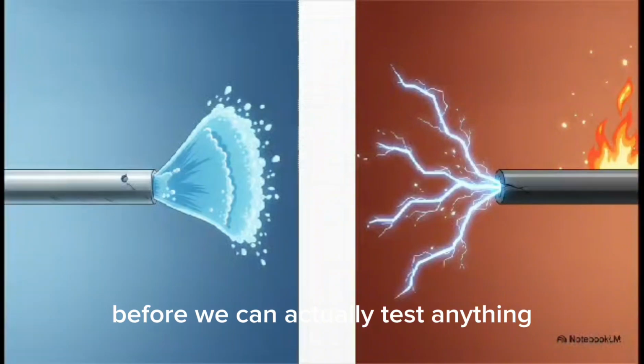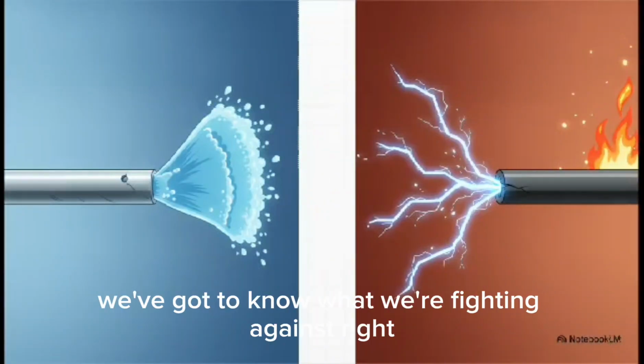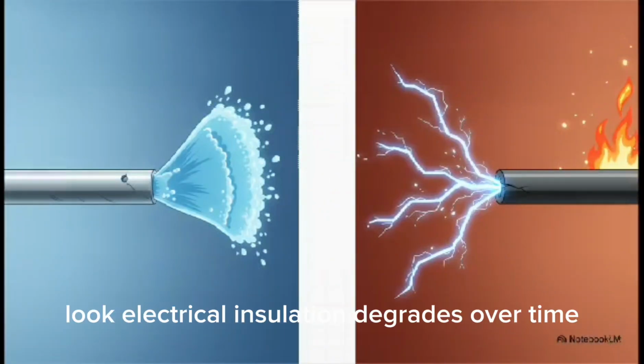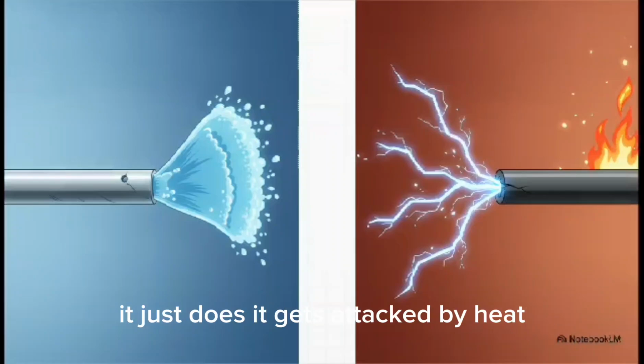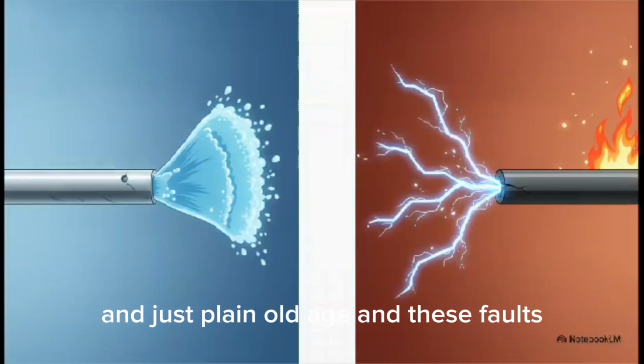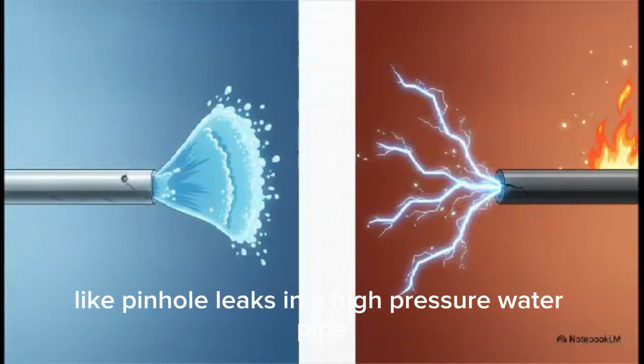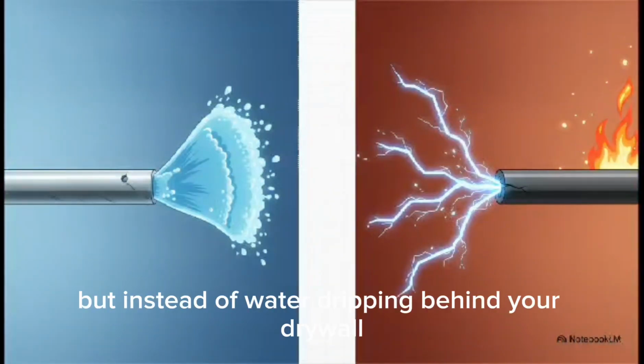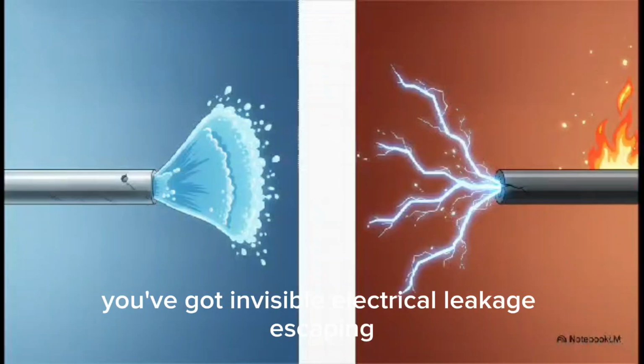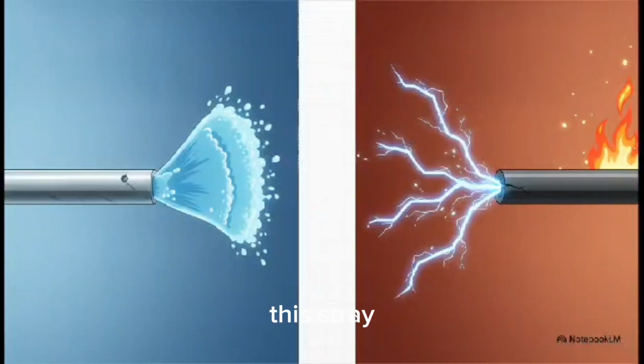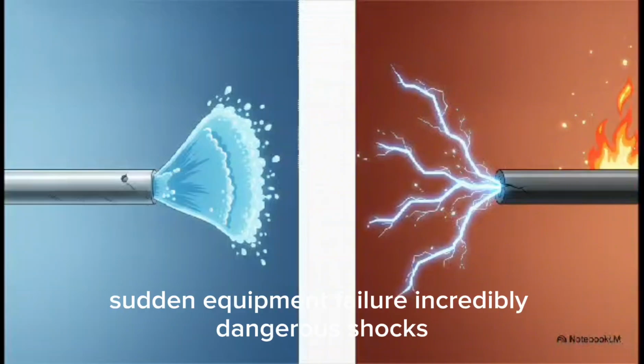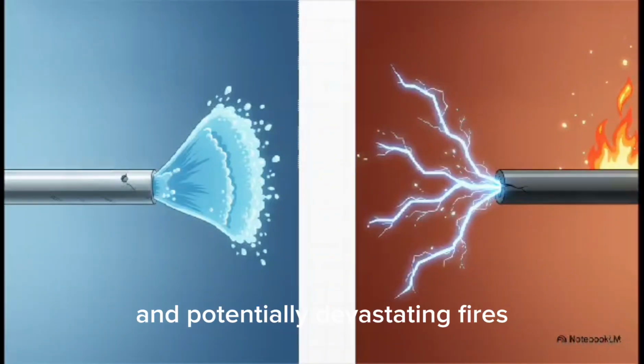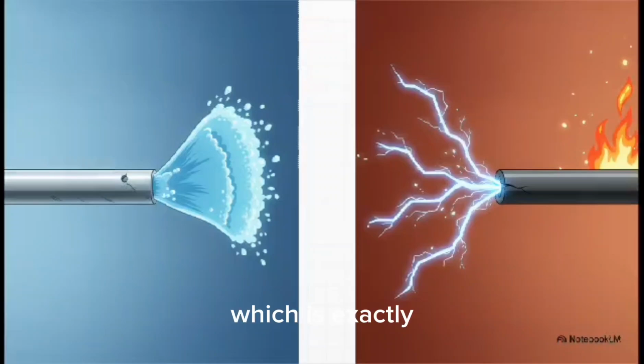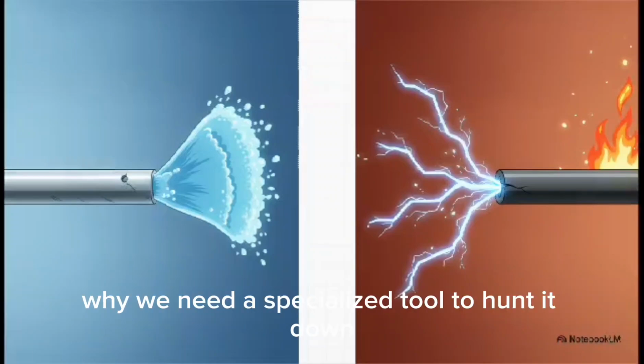Before we can actually test anything, we've got to know what we're fighting against, right? Look, electrical insulation degrades over time. It just does. It gets attacked by heat, moisture, dust, and just plain old age. And these faults act exactly like pinhole leaks in a high-pressure water pipe. But instead of water dripping behind your drywall, you've got invisible electrical leakage escaping. This stray electricity is exactly what causes sudden equipment failure, incredibly dangerous shocks, and potentially devastating fires. It's a completely invisible threat, which is exactly why we need a specialized tool to hunt it down.